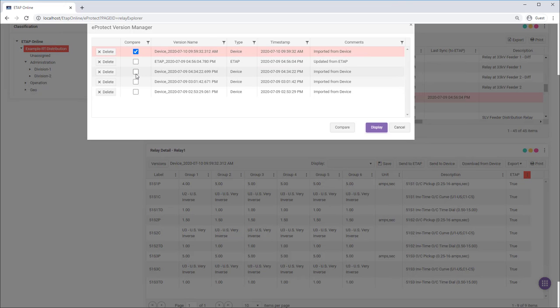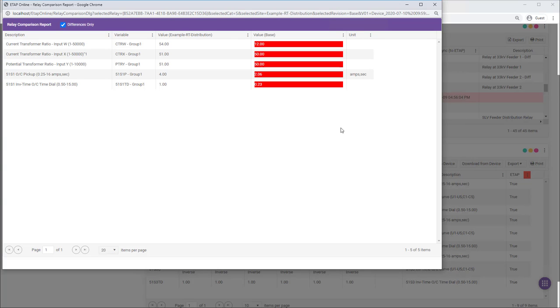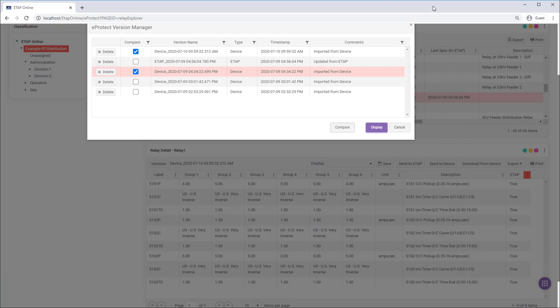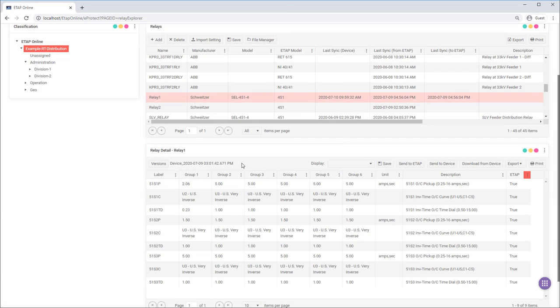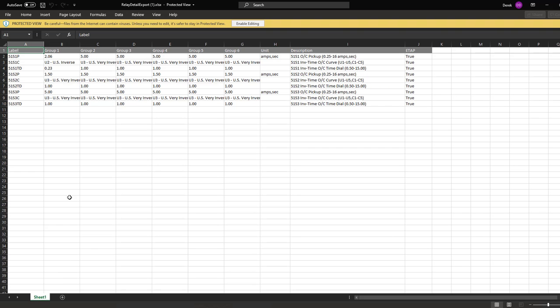The version manager compares different settings from different time periods, and I can compare and see the overcurrent pickup was changed. Historical settings are stored and can be pulled to view in the main table. So I can select which one I want, hit display, and my table is updated with historical information. And the relay settings can also be exported to Excel directly from eProtect.